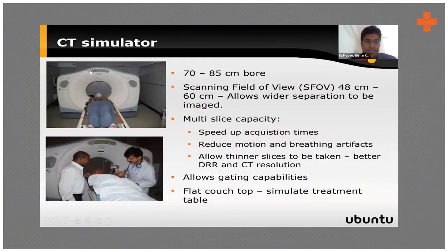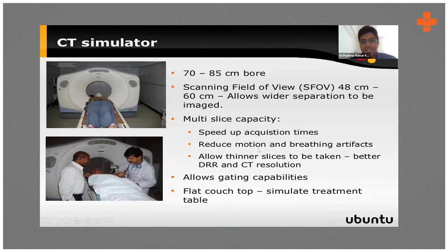This is an example of a CT simulator, which we generally use every day to capture data. The CT simulation scans used for planning are similar to our diagnostic CT scans, but with a slightly larger bore of about 85 centimeters. We can customize the number of slices and how thick or thin we want them.